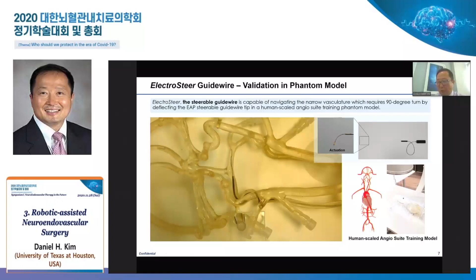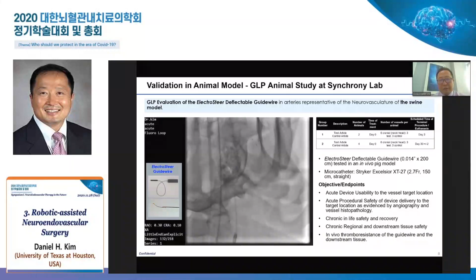Like I told you before, in order to get FDA approved, we had to do a GLP animal study using swine models, and it met all the biocompatibility, electromagnetic EMC testing, and packaging, sterilization, and all of the things the FDA is demanding. But what I would like to share with you is that it has a platinum iridium coil for radiopacity. As you can see here, radiopaque marking, because electroactive polymer is radiolucent.